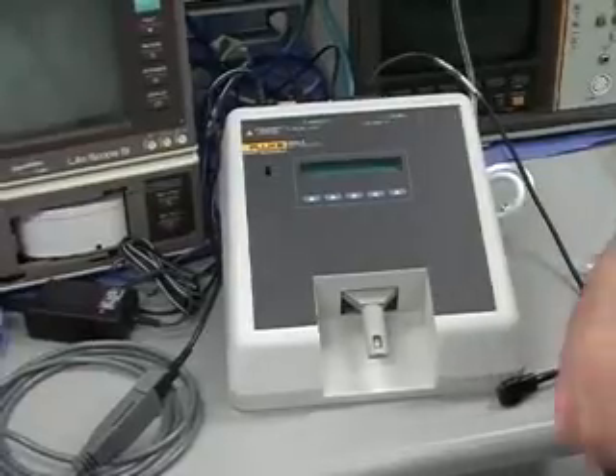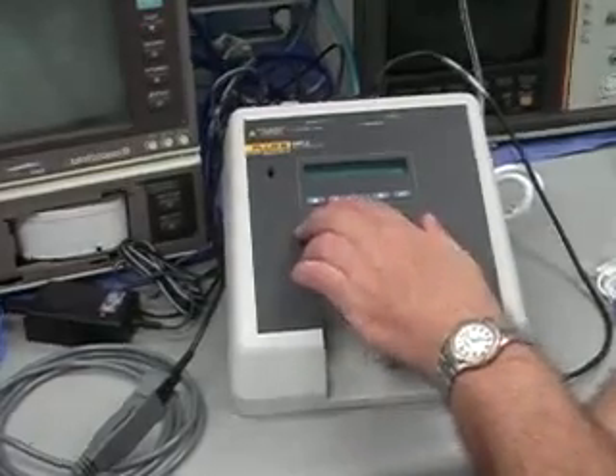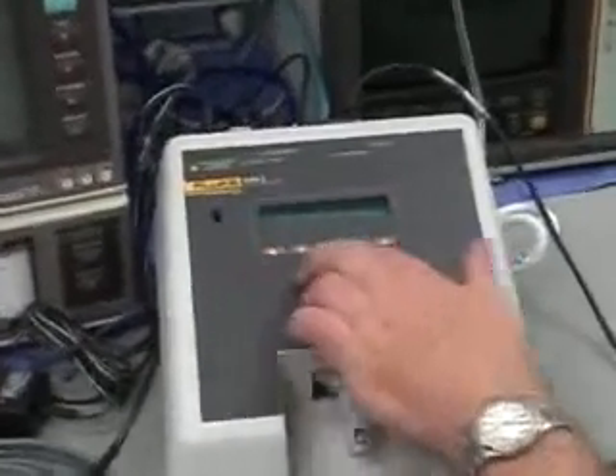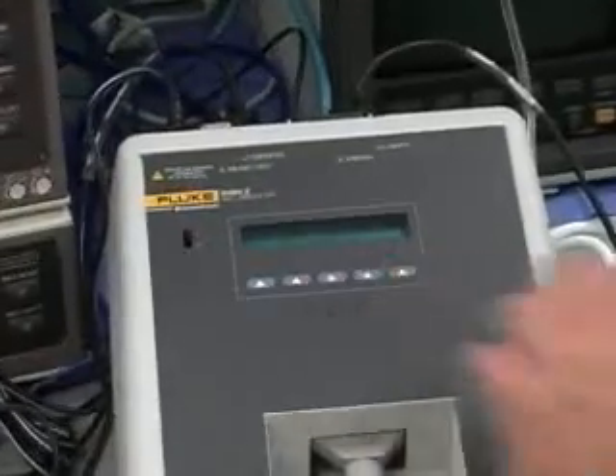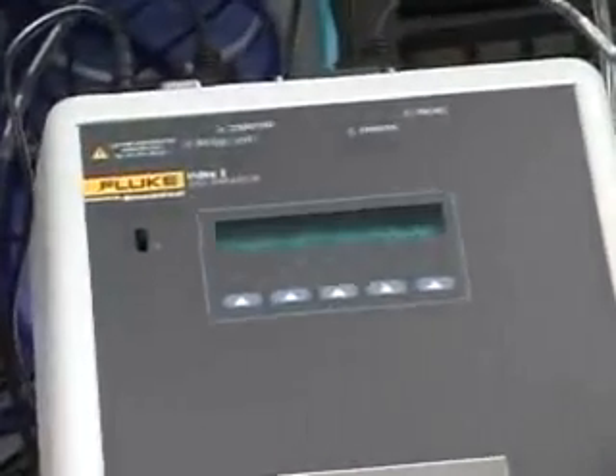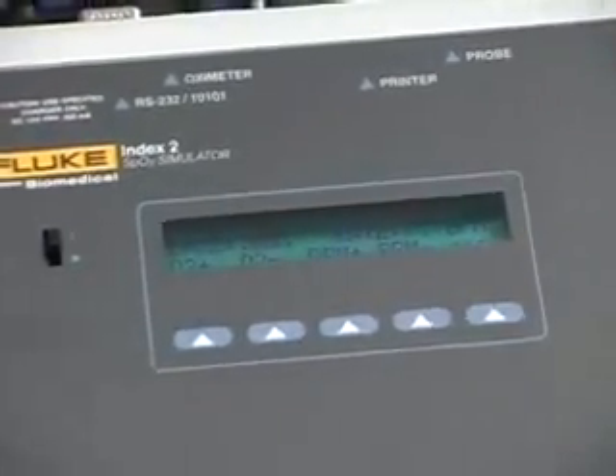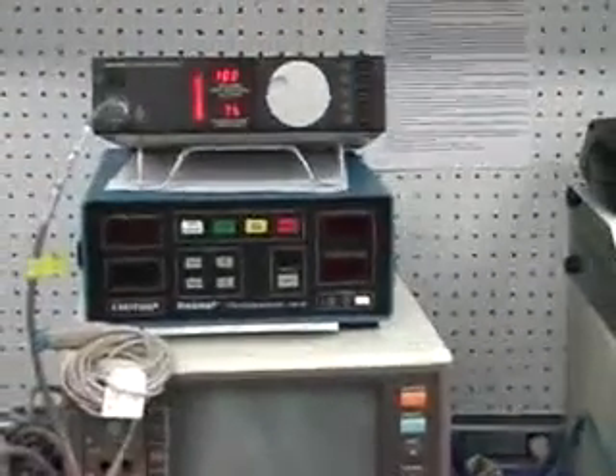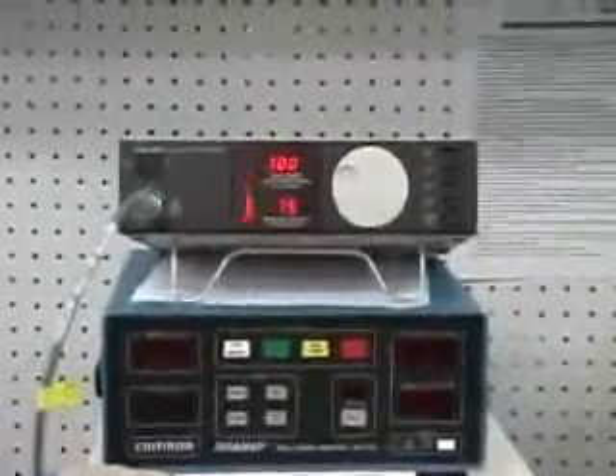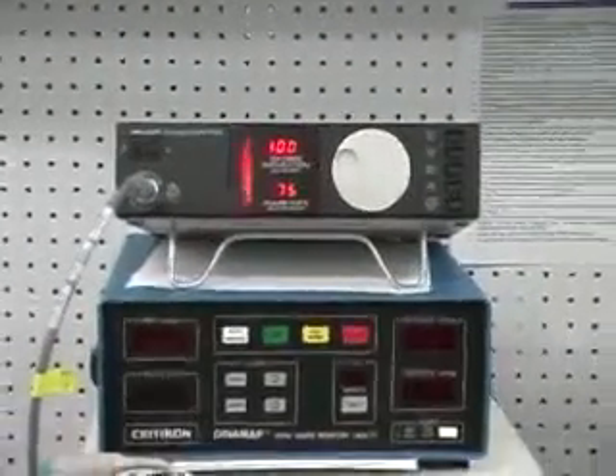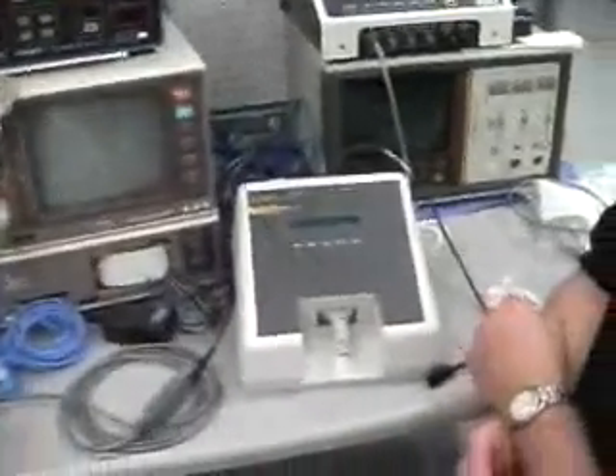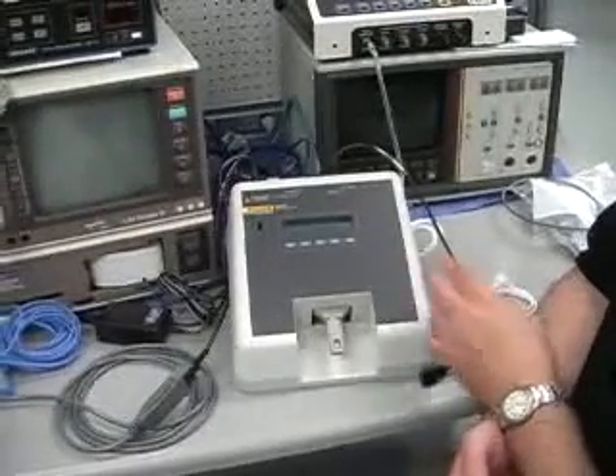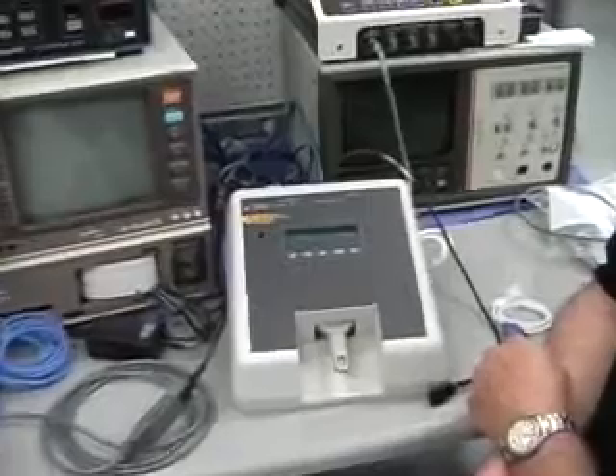Okay, with this you're able to adjust saturation levels. You can go all the way up to 100, and usually this is an average responding system, so it's going to take a few beats for it to catch up. Everything is working quite well here. For basic calibration, 70% to 100% is really the calibration range on these. Yes, you can run at lower values, but as with many pulse oximeters, those are uncalibrated levels.